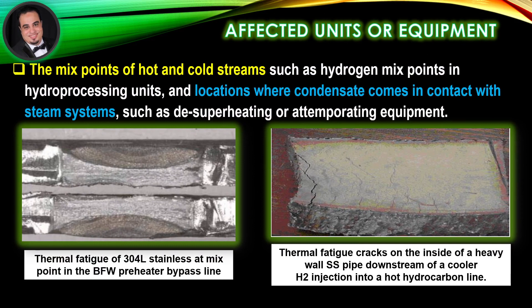Affected units or equipment examples include the mix points of hot and cold streams, such as hydrogen mix points in hydroprocessing units, and locations where condensate comes in contact with steam systems such as de-superheating or attemporating equipment. This includes thermal fatigue of 304L stainless at a mix point in the BFW preheater bypass line, thermal fatigue cracks on the inside of a heavy wall stainless steel pipe downstream of a cooler, and hydrogen injection into a hot hydrocarbon line.